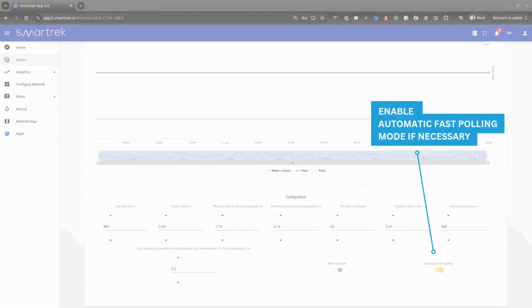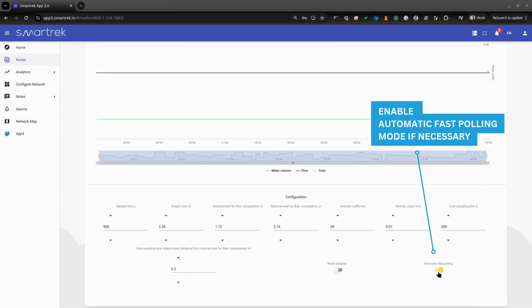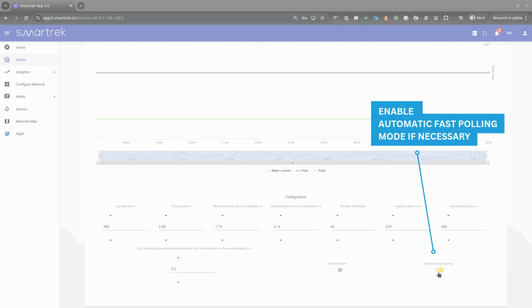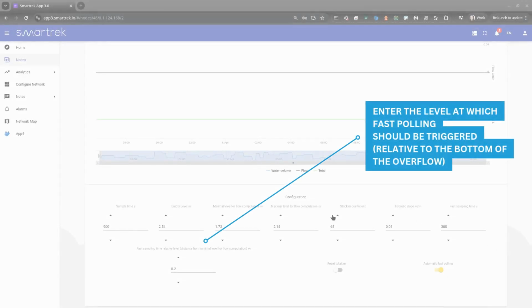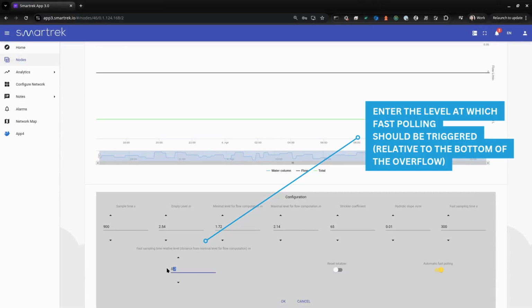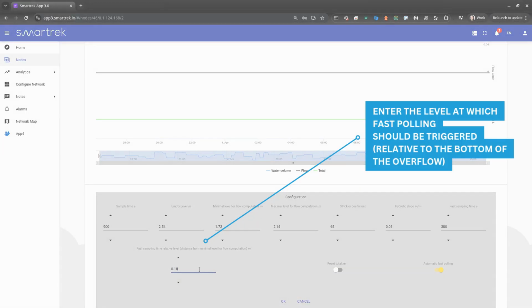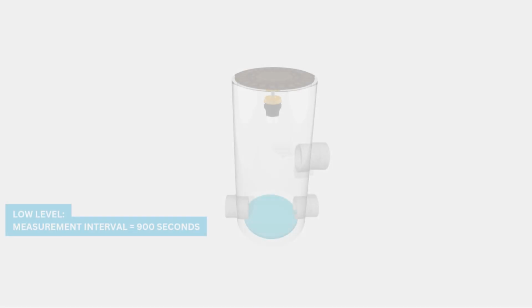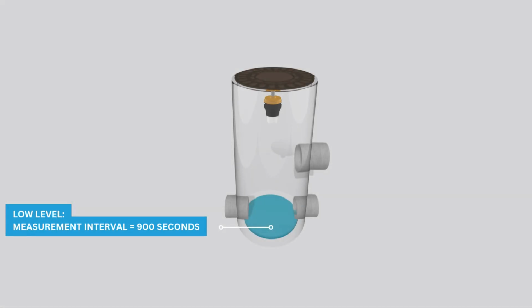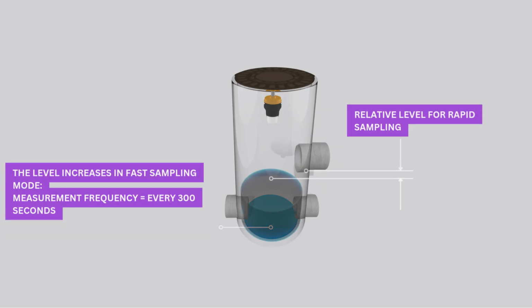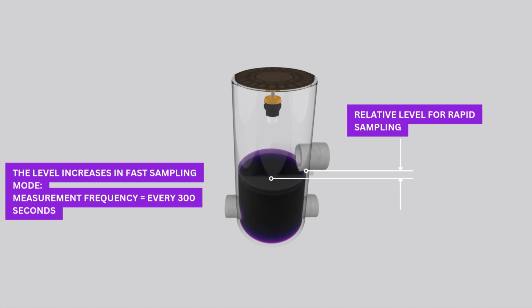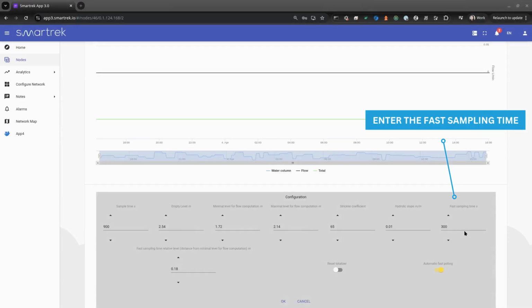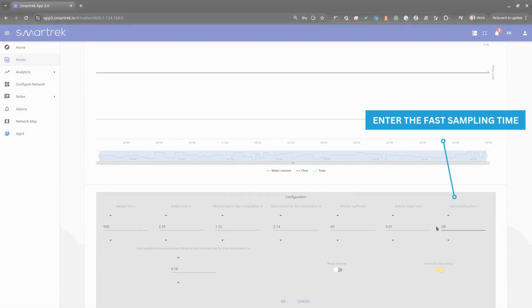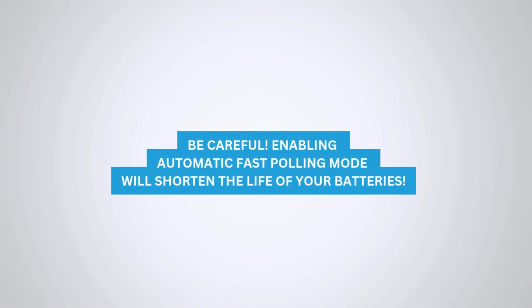If you'd like the sensor to take more frequent readings when the water level is high, enable automatic fast polling. Then, in the fast sampling time relative to level field, enter the distance from the bottom of the weir at which the measurement frequency should increase. This way, when the water level is low, readings are taken every 15 minutes. When the level reaches the relative level for fast polling activation, the reading frequency increases. Set your desired fast frequency in the fast sampling time field. Be careful. Enabling automatic fast polling mode will reduce your battery life.